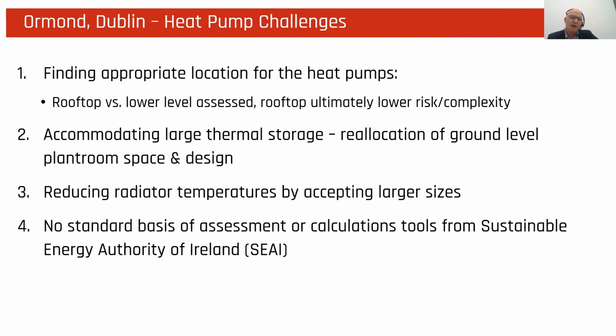So in order to accommodate this thermal storage, we redesigned the ground floor level. And as part of the air source heat pump, the 8 heat pumps, we matched that with 8 250 kilowatt Hamworthy boilers. And in fairness, Michael's previous presentation fed into Ormond completely. We ended up with 27 cubes of hot water, and we chose to come to the lower 60 degree generation staging.